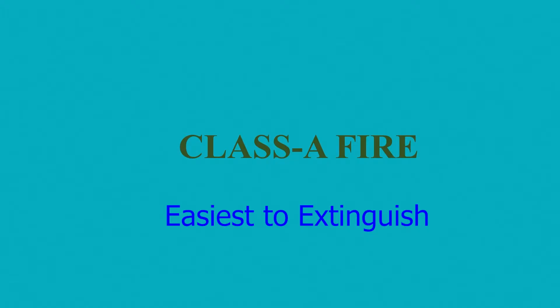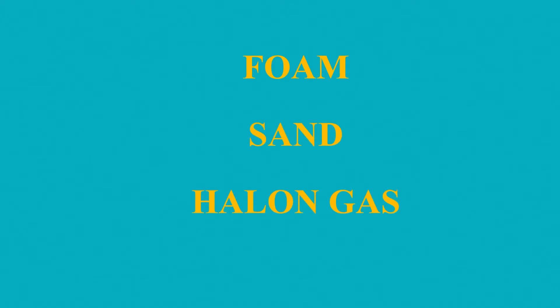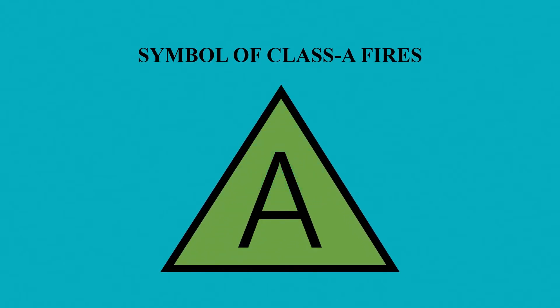Class A fires are the easiest type to extinguish. These fires are extinguished by taking out the heat element of the fire triangle. Mostly water is used to extinguish Class A fires. In extreme cases, foam, sand or halon gas can also be used. Class A extinguishers are identified by a triangle symbol in green color with a capital letter A.